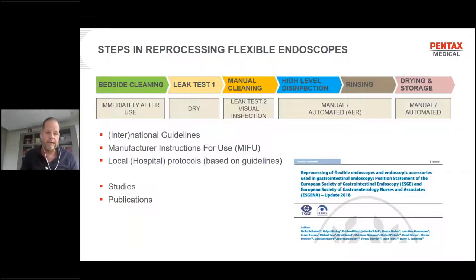I assume we all know these are the steps in reprocessing flexible endoscopes. It starts with bedside cleaning, then the dry leak test, then manual cleaning, also with a leak test and visual inspection, followed by high level disinfection with a detergent and a disinfectant. Then, of course, rinsing, and it was also pointed out in Ulrike's presentation, the drying and storage, which is also very important and becoming more important.